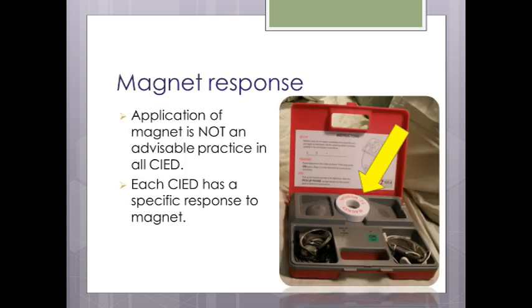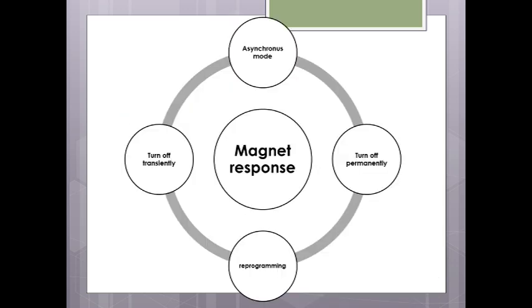Magnet application is not universally advisable because each CIED has a specific, device-dependent response known to the electrophysiologist. The magnet may convert the pacemaker to asynchronous mode (desirable), turn it off permanently (undesirable), turn it off transiently, or cause unexpected reprogramming. Always confirm anticipated magnet response with the electrophysiologist beforehand.